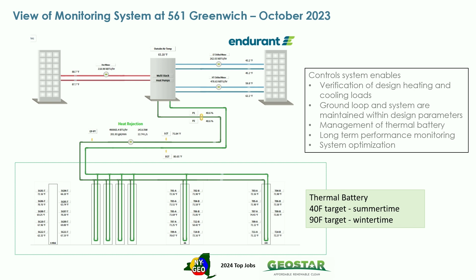Come February 2024, one of the coldest days of the year in New York City, you can see the temperature at the top—it was about 24 degrees Fahrenheit. What we're getting out of the ground is about 55 degrees. Importantly, if we'd been using air source heat pumps at that time, the efficiency would have been 2.9, but those ground source heat pumps at 55 degrees coming out of the ground were operating at an efficiency of 5.7, a COP of 5.7.